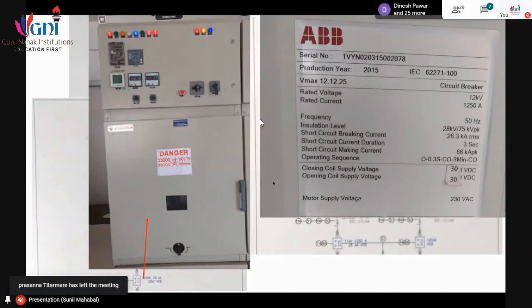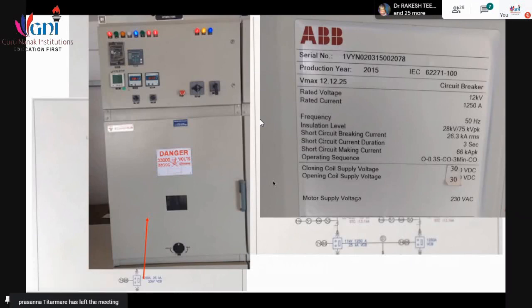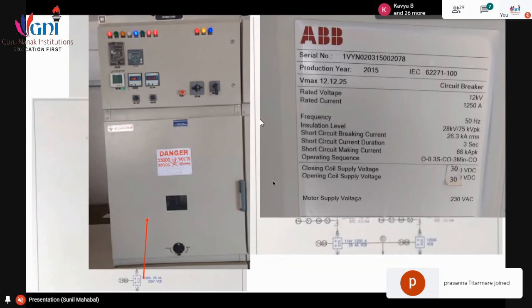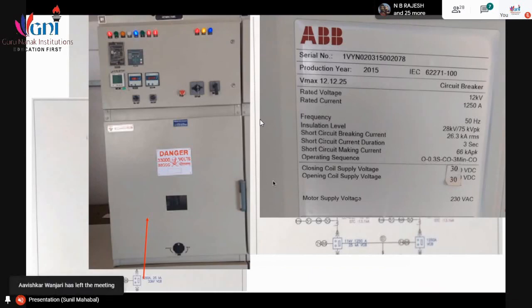That is the breaking capacity of the circuit breaker. Whereas the making current, when this fault is already existing in the field, a phase-to-phase short or phase-to-earth short, and we are trying to switch on the ACB or VCB, then the huge current will immediately flow through the contacts. That is the reason why making current is 66 kiloampere and breaking current is just 26.3 kiloampere.